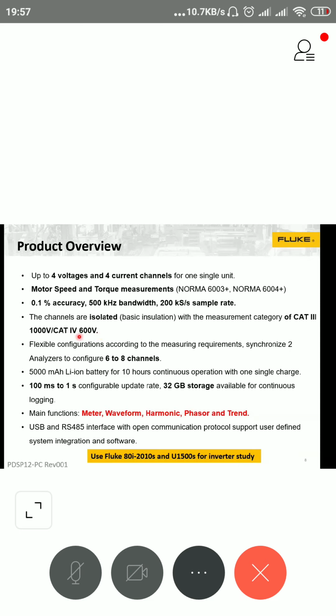Now, your instrument, either a multimeter or a power analyzer or any equipment, should have the category 4 safety rating. When it carries a category 4 safety rating, it means that the equipment can withstand up to 8 kilovolts impulse, that spike. Right? And so this equipment is carrying category 3 and category 4. So you can use it outside in the field or inside the lab.